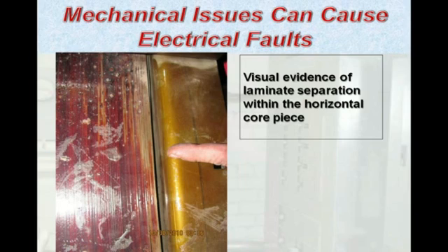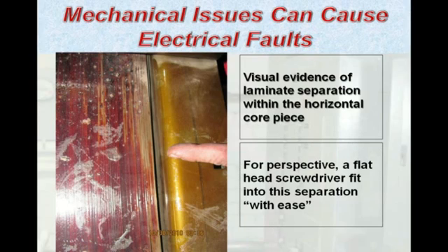Looking at the top section, the laminate separation is even more clear. Right where the technician's finger is pointing, you can see the separation between the steel and the laminates there. That should be nice, tight, snugly fit up against there to contain the magnetic lines of flux. For perspective, on this particular gap, you were able to take a flathead screwdriver and with ease stick it down into this opening. So the separation was not minor by any means. It was moderate to severe at this point.